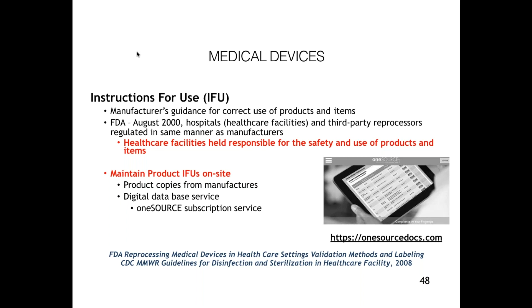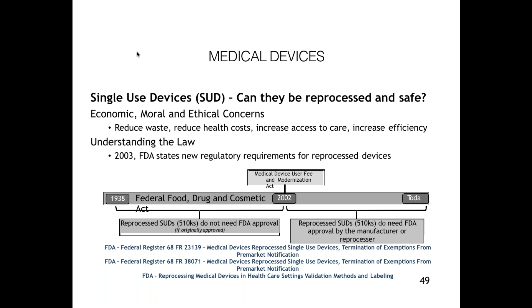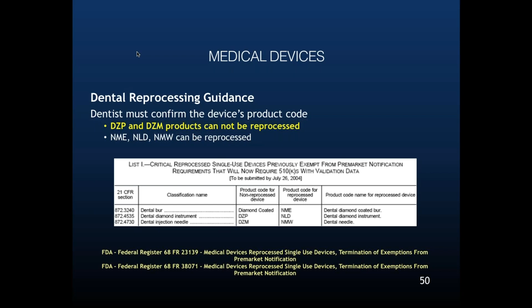So the first thing to realize is the FDA defines the regulatory requirements, which means they say we do. So that's the first thing. If they say single-use devices for certain things, you have to use single-use devices. It's wickedly expensive, but if they say so, we do. All right. So when you go to the FDA, there's actually a whole set of things. You have to look at what the product code is. And if they have D codes, you can't reprocess them. So that's going to affect a lot of our diamond burrs. But if they have N codes, they can be reprocessed.